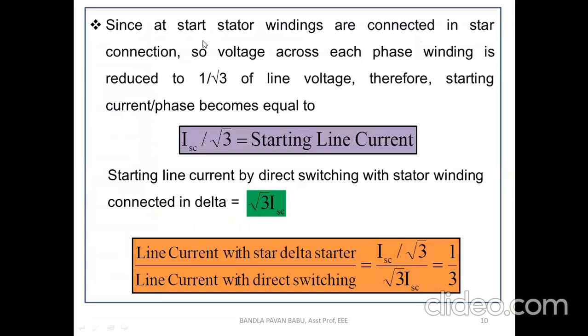Since at start the stator windings are connected in star connection, the voltage across each phase winding is reduced to 1 by root 3 of the line voltage. We are not using any control method there; directly, just by using the changeover switch, we are connecting in star connection. So what happens in star, the phase voltage is 1 by root 3 times the line voltage. Therefore the starting current per phase becomes ISC by root 3, which is the starting line current.